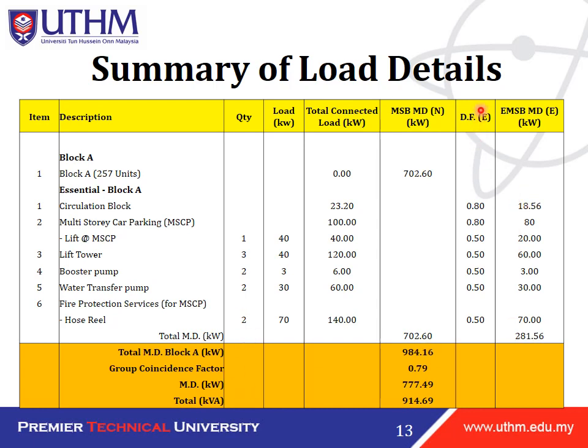This is the example of summary of load details. So we have block A with 257 units, and then we have the essential block A which consists of circulation block, multi-story car parking, lift tower, boost pump, water transfer pump, fire protection service with their respective quantity and load. From there we can calculate the total connected load, demand factor and the maximum demand. So this is what you have learned in the previous chapter. So you can double check your understanding by calculating the total maximum demand, group coincident factor, maximum demand, and also total in kVA.